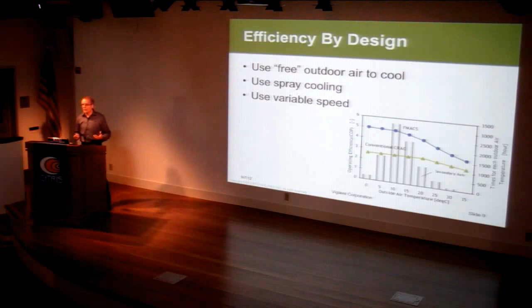But that doesn't necessarily get you an efficient data center, because you can destroy those savings through bad operation—or rather, through operating practices that waste energy and interfere with the efficient design that was intended. Running always on, always cold is clearly not an efficient way to operate your data center. You don't need full cooling capacity running if you don't have full load capacity, and most facilities don't.